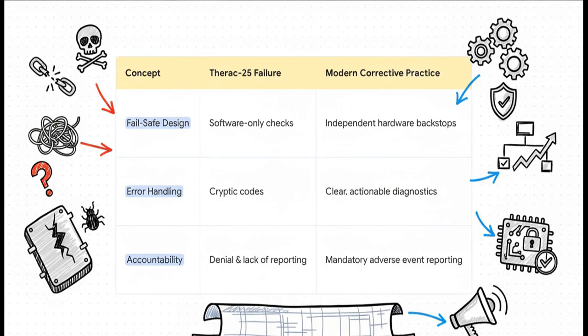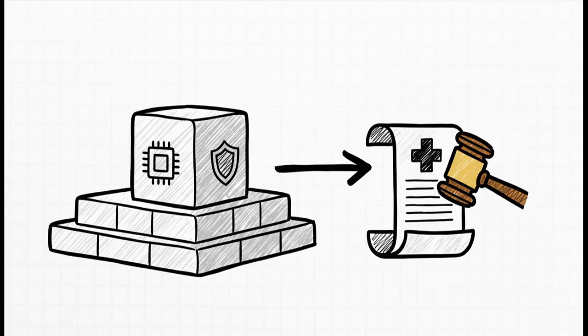And you can see here how directly the failures map to modern best practices. The story of the Therac-25 literally became the blueprint for what not to do. Every mistake, relying only on software, using cryptic error codes, denying reports, led directly to a new rule, a new standard, or a new law designed to prevent it from ever happening again. Ultimately, this tragedy had a lasting legacy. It's now a required case study in software engineering and medical physics programs all around the world. It also directly led to new legislation, like the Safe Medical Devices Act, which mandates accountability. The lessons learned from the Therac-25 are now literally written into law.